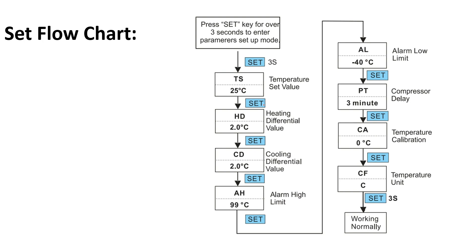After heating differential, the user sets the cooling differential value, alarm high limit, alarm low limit, and PT — the preset compressor delay time. CA is the calibration factor, which is an offset added or subtracted from the temperature measured by the sensor. Finally, the unit can be set. To exit, press the SET key for three seconds and the parameters will be saved.